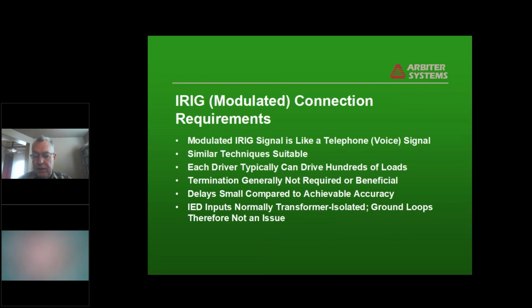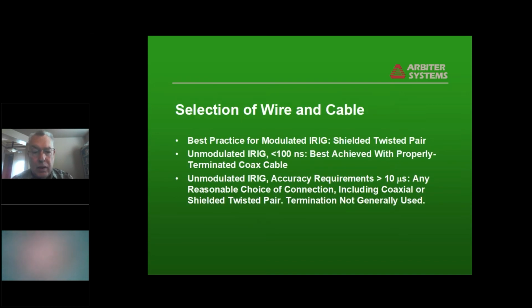They also have automatic level control on the receiving end so the signal level isn't very critical. And the delays on the wiring are small compared to the achievable accuracy, which is limited by the way it's encoded and the relatively slow slew rates of the 1 kilohertz signal. So the delays aren't really of much consequence. For modulated IRIG, we recommend using a shielded twisted pair, but you can use pretty much any twisted pair if that's what you have available.